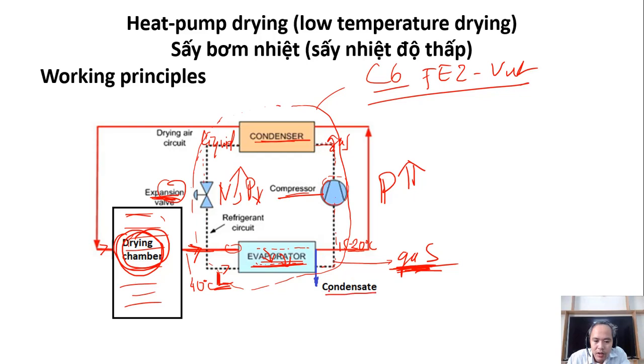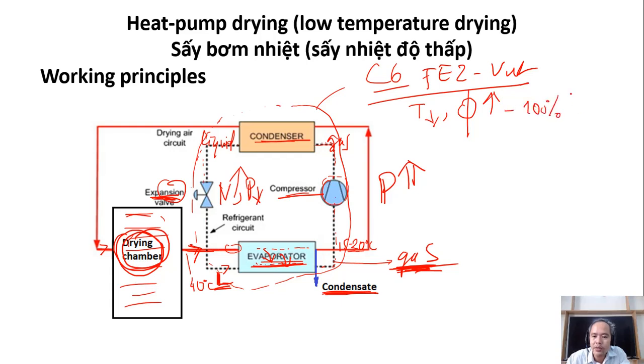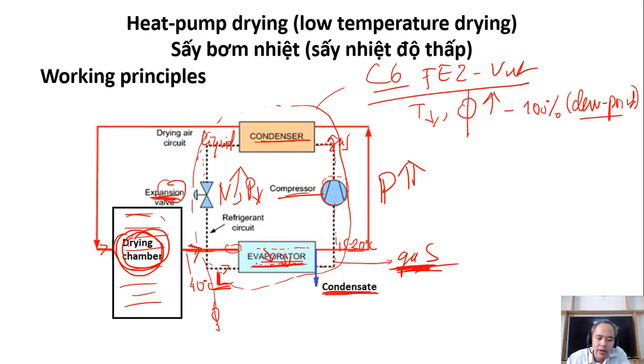When the temperature drops, the relative humidity increases. When it increases to 100%, you reach the dew point. If you go further below the dew point — since this air has a very high relative humidity, the dew point may be around 30°C — but you go below it, so part of the vapor condenses into liquid. Condensation occurs in the air.